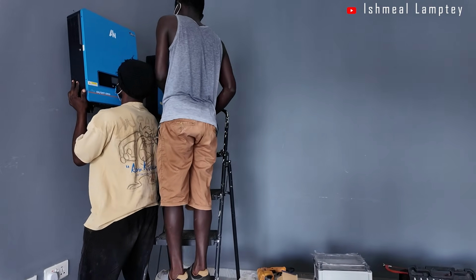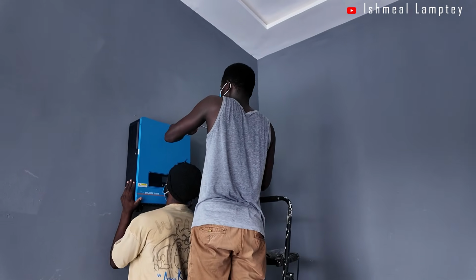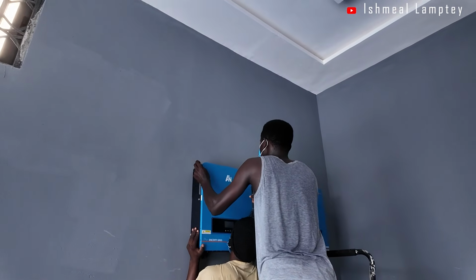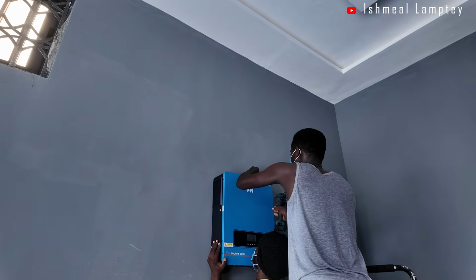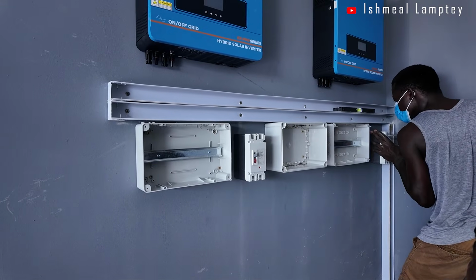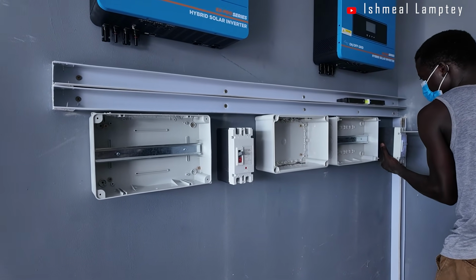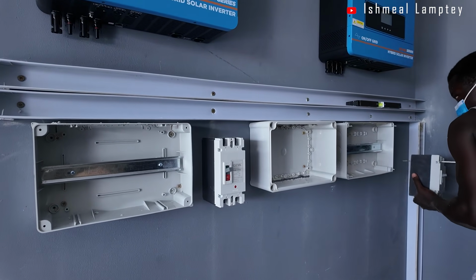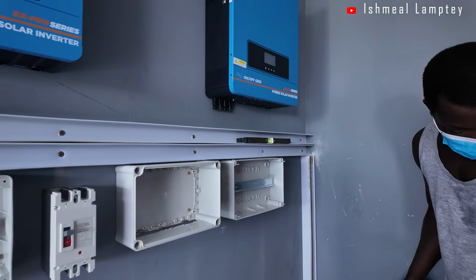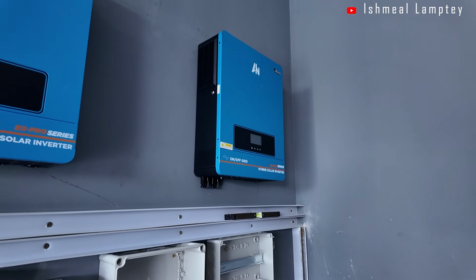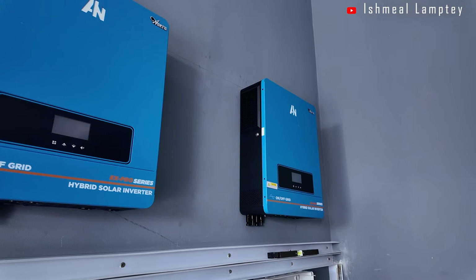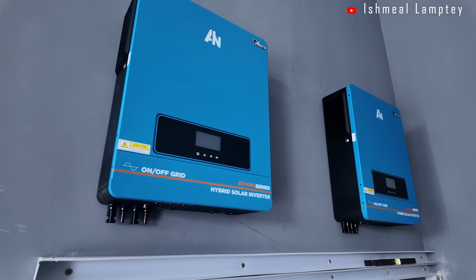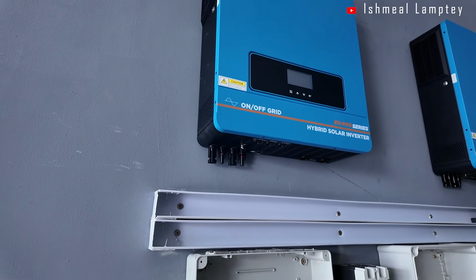The first part was mounting the inverter itself. As part of that, we also had to mount the breaker boxes - we mounted two different breaker boxes, one for the left inverter and one for the right inverter. For this setup, usually when you have two inverters, it means you're putting them together to serve as one system.